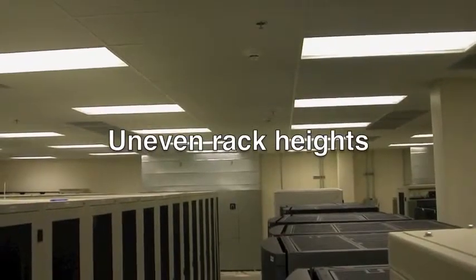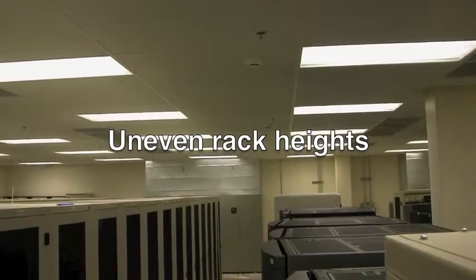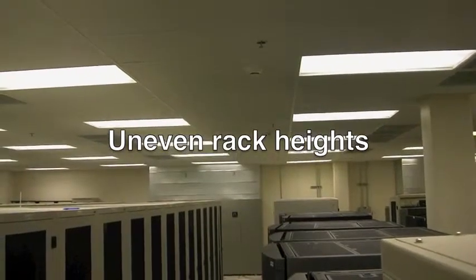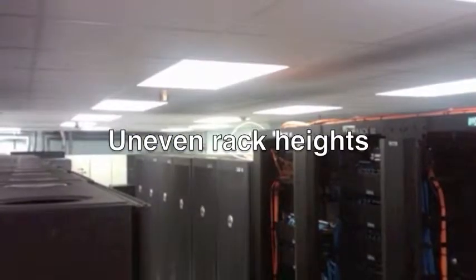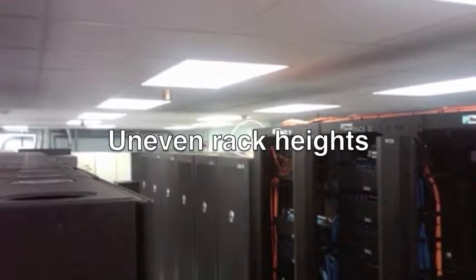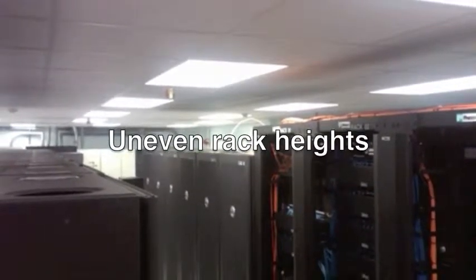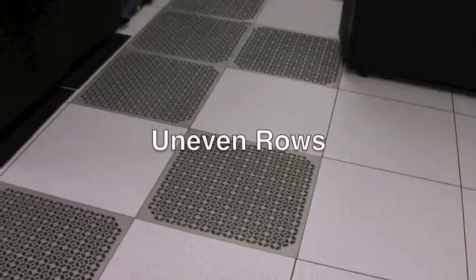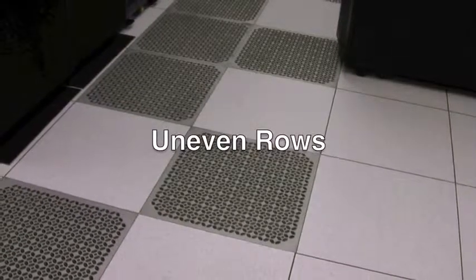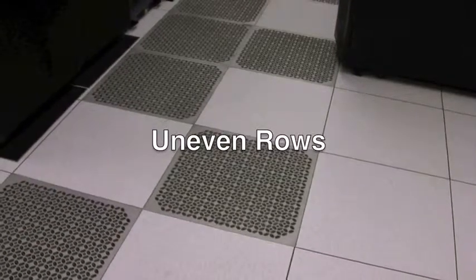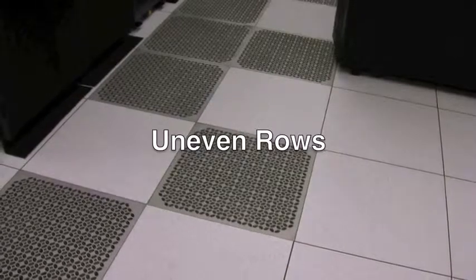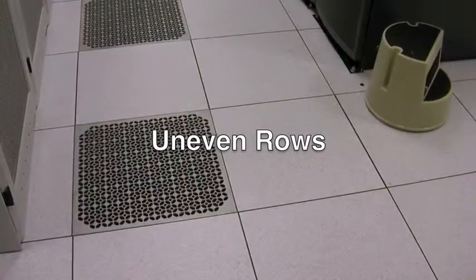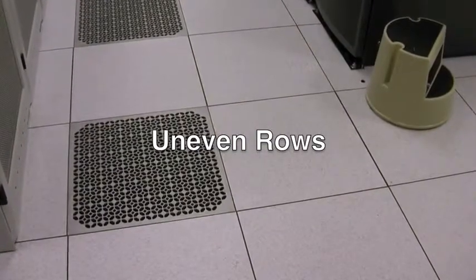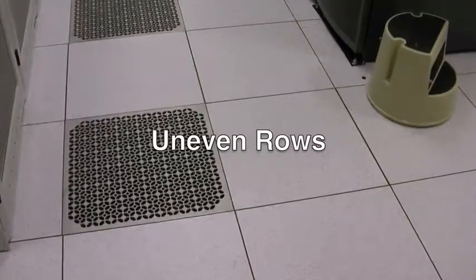The first category of conditions we have to look at are uneven rack heights. That's not so much a problem when you're hanging curtains from the ceiling because you can trim the curtains to the different heights, but it needs to be accommodated when you're doing the rigid panels across the top. Then of course, lots of times we see uneven rows. So again, when you're putting a door across the end of the row, you need to accommodate that gap between the last rack and where that door is.